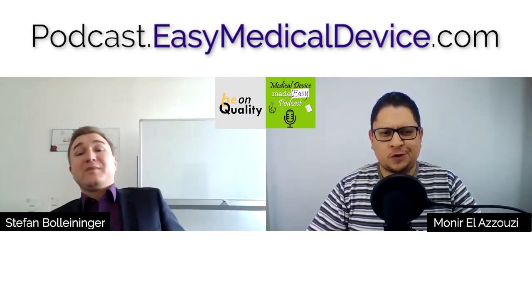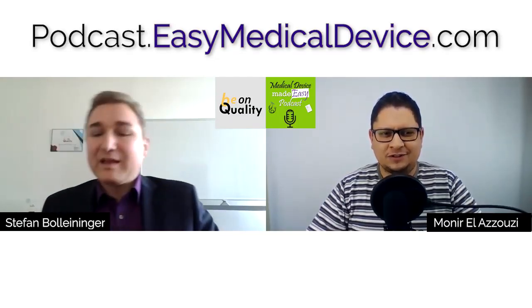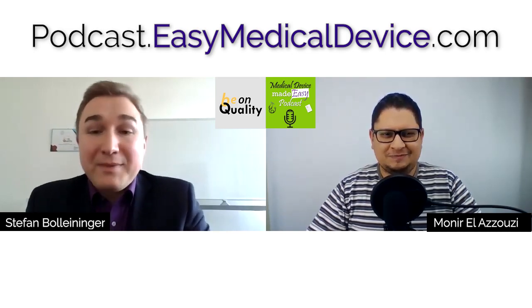And surprise, for those that are under MDR, we have the possibility of an unannounced audit. Will it cover also the ISO 13485 or not? Well, that's a completely different approach, because the regular audits shall tell you, I have a robust working system. So the unannounced audit tells me, I know that you have regularly checked your quality management system, but you do not have only a quality management system, you also have products. And the unannounced audits focus specifically on one or more products.